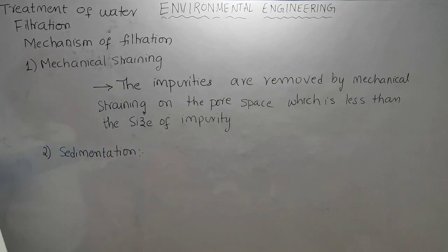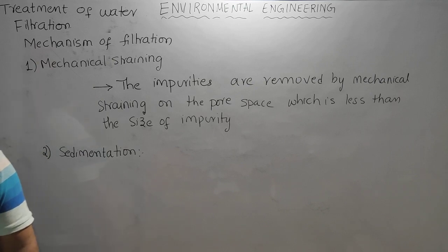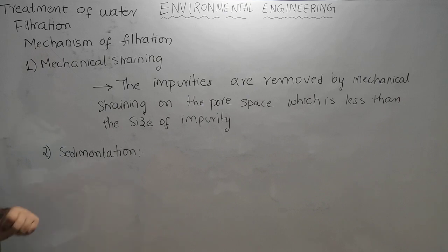If you understand very specifically, in mechanical straining, particles having size more than the voids get removed, whereas the continuous voids present in the filter media will act like tube settlers and arrest the finer particles than the pore size also.